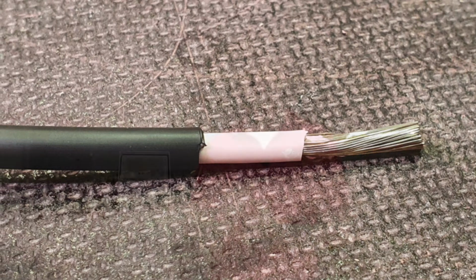It's also important to keep the earth reference away from any existing connections to the greater mass of earth, such as may be found near the incoming supply, or any extraneous conductive parts. The reason for this is that under fault conditions, the rising voltage on these items can cause a rise in voltage on the reference electrode and reduce the effectiveness of the charger, monitoring the potential difference between the CPC and the earth.